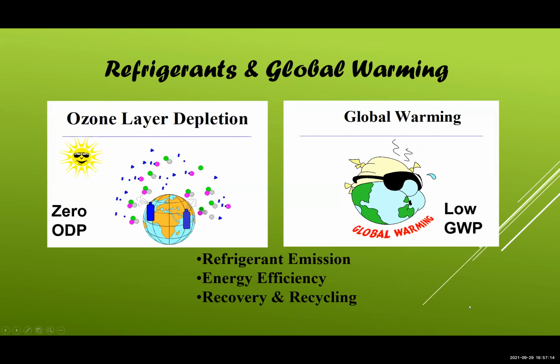And when we talk now about refrigerants, we have to deal with two major parameters, issues, that is ozone layer depletion and global warming. So when you say ozone layer depletion, as was mentioned by Omar, we have almost phased out ozone depleting refrigerants, but still there are like R22, R123, they are all ozone depleting refrigerants. So we are yet to completely phase them out. Then we have a global warming issue. That means it is characterized by GWP.